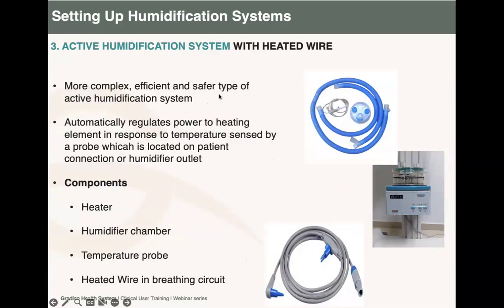Okay, so now we come to the second type of active humidification system, which has a heated wire. As you can see on the lower picture with the gray wire, this is a wire which is connected to the humidifier. And the good thing about the heated wire type of humidification is that it has a thermometer, so it can auto-regulate the temperature. And that's why they recommend it in pediatric, because mostly in pediatric we are afraid of hypothermia because of those breathing circuits.